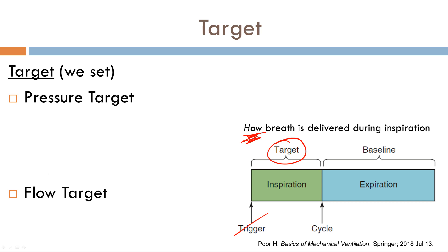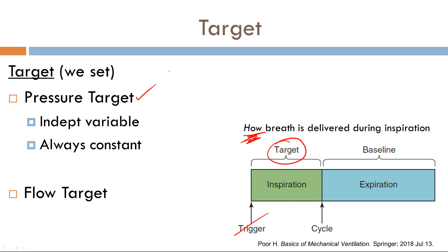Let's start with the pressure target. Here, pressure is your independent variable — it is constant, it is something that we set. Every time we set it, the amplitude is exactly the same. For example, I can set a pressure control of 20 centimeters of water and every single breath the pressure will be 20. Here pressure is your independent variable; however, flow will be your dependent variable and will vary with every single breath.